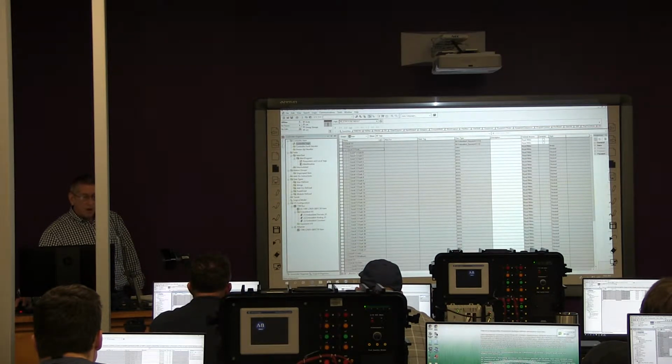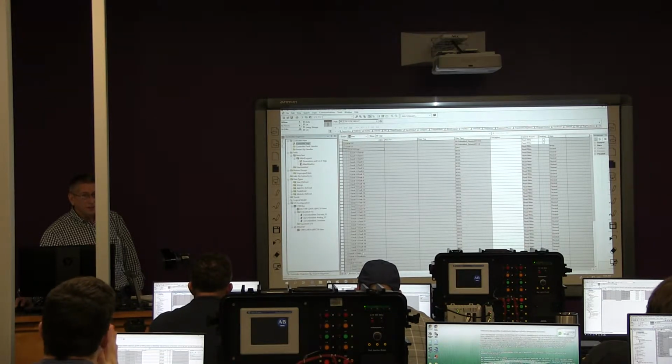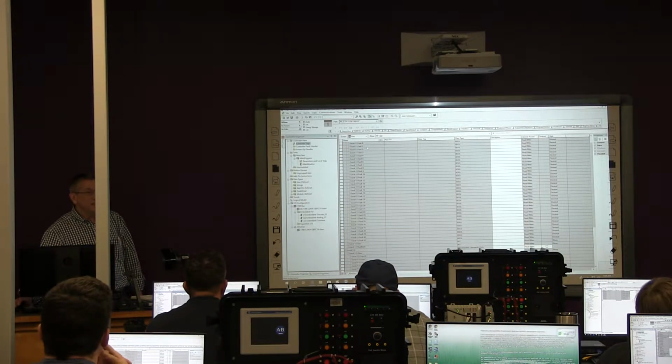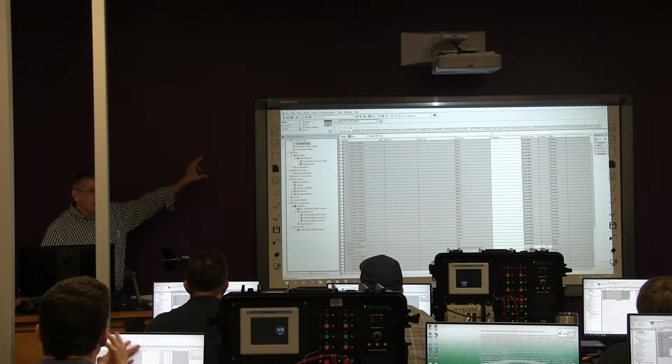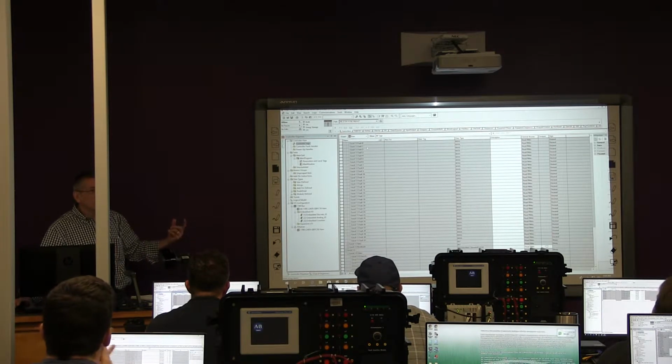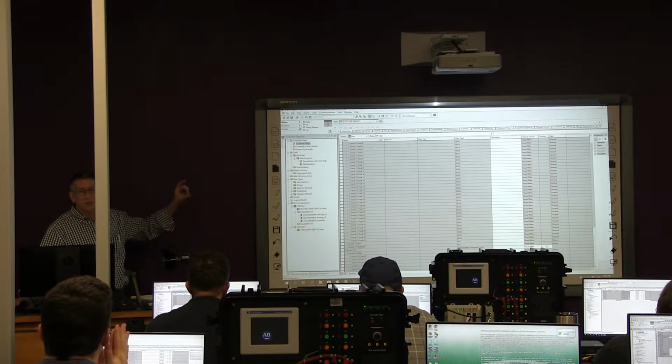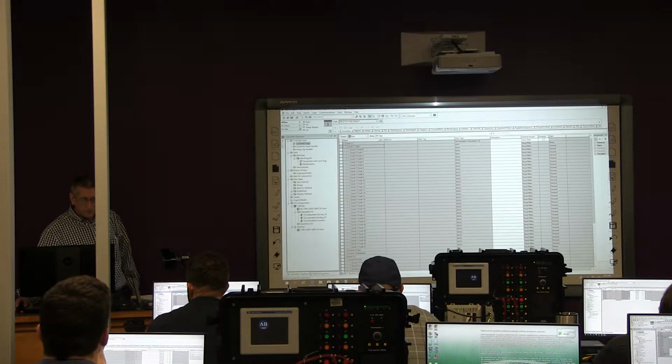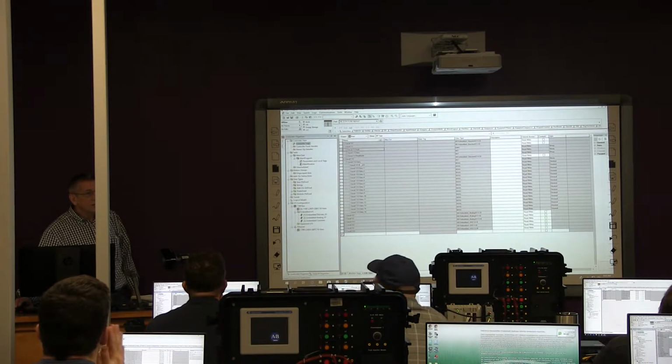Local 1I fault, we have how many bits? 32 bits. You think that's just a coincidence? That's right. So that's the fault data for both all your inputs and your outputs. That makes sense? They're using one double integer, 32 bits, for the 16 inputs and the 16 outputs. Clear as mud now?